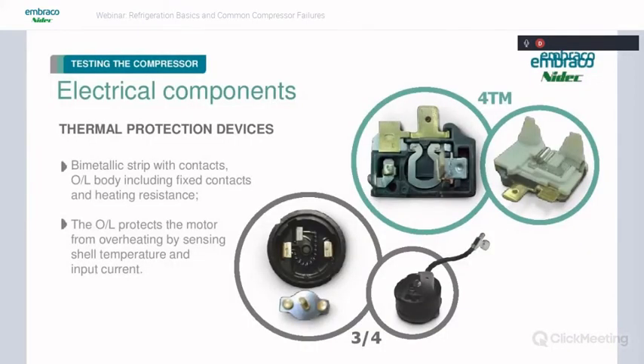And then we have our overload protectors or thermal protection devices. These are designed to protect the compressor motor from any kind of overload, mostly heat or high discharge pressures, things like that. But they're designed to be an on-off device to disconnect power to the compressor in the event of an overload. And the way they do that, your typical one is the 3/4 round, also called the Klixon a lot of times.